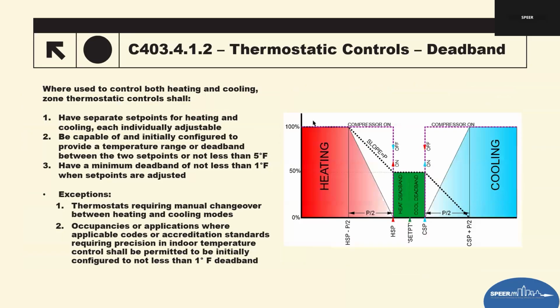R2 buildings. So for any zone that controls both heating and cooling, the point of these controls, looking at thermostatic controls, deadband, is basically to avoid simultaneously heating and cooling and to ensure the system operates efficiently within a defined temperature range. And to do that, the controls must have separate heating and cooling set points. The first requirement is that the thermostat must allow separate set points for heating and cooling. They cannot share a single combined setting. Both must be individually adjustable by the operator or occupant unless overridden by a BAS.